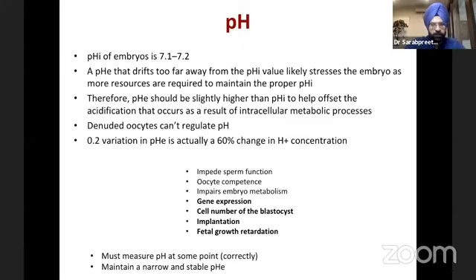You should always measure pH at some point of time, like we do it every 3 months in our lab, and then we use our CO2 analyzer to check. Another way of doing it is you can check your dry gas supply. If your supplier is good, then you can calibrate your CO2 analyzer by checking the CO2 in the dry gas cylinder. If you're confident that he's supplying 6%, you can adjust the other incubator accordingly. You should maintain a very narrow and stable pHe.